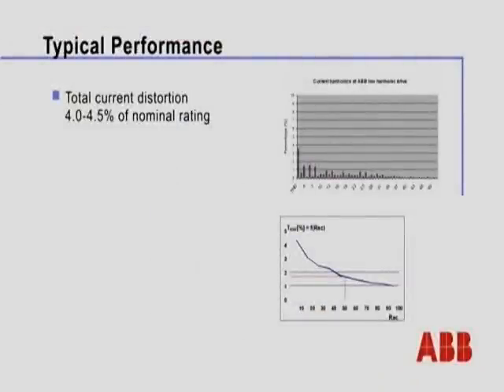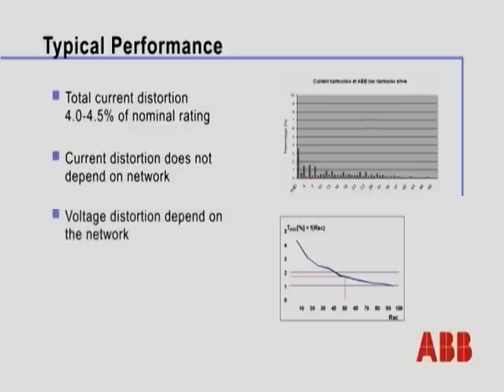You know the wide-ranging ABB product offering in the ULH, but why this particular product instead of some other? Well, the primary reason for an ultra-low harmonic drive is, as its title states, low harmonics. The ULH drive provides the lowest available harmonic mitigation of all of the different technologies out there. Total current distortion is typically 4 to 4.5% of the nominal rating of the drive. Current distortion does not depend upon the network. And while IEEE 519 calls for these types of measurements at the distribution transformer, we can also provide the lowest level of harmonic distortion at the drive input terminals.